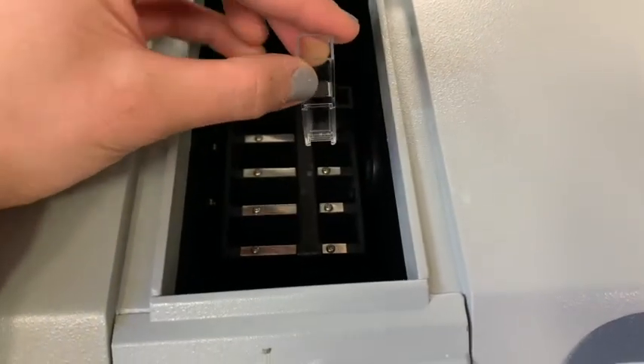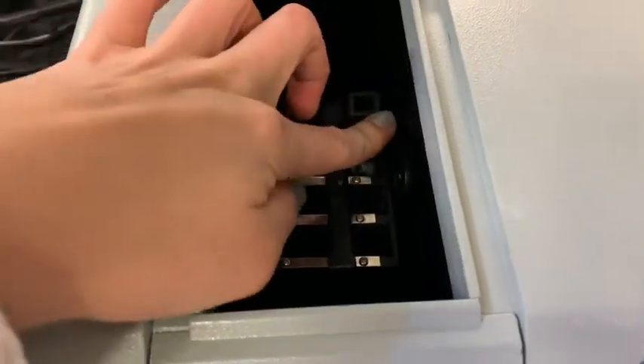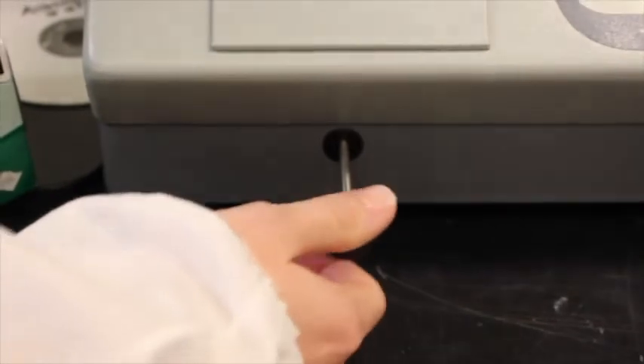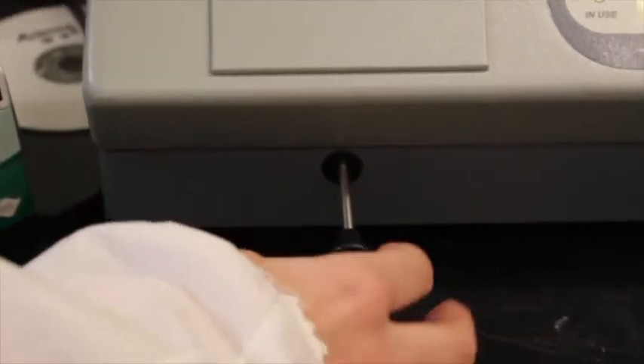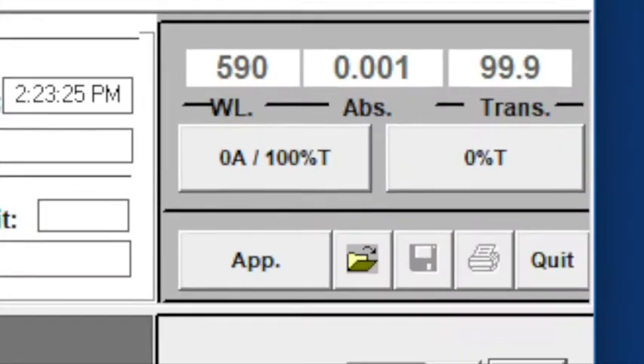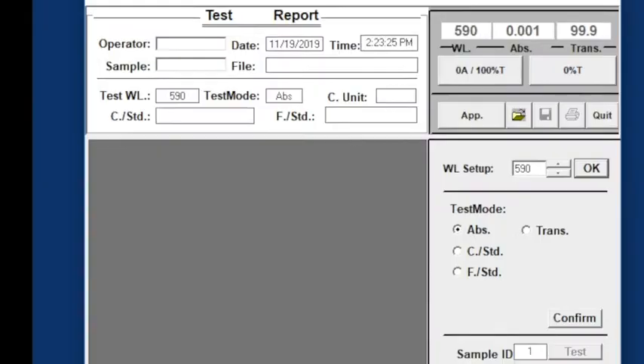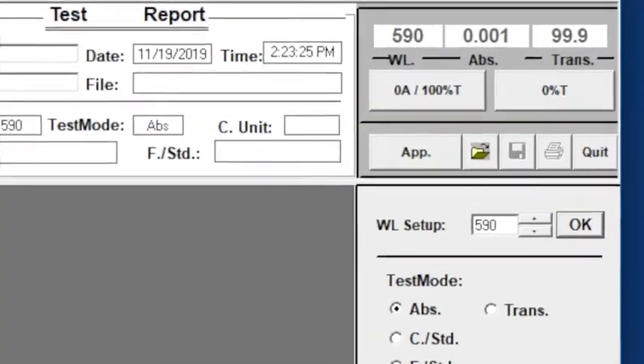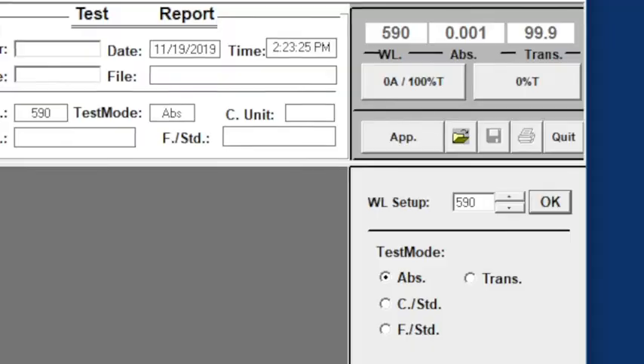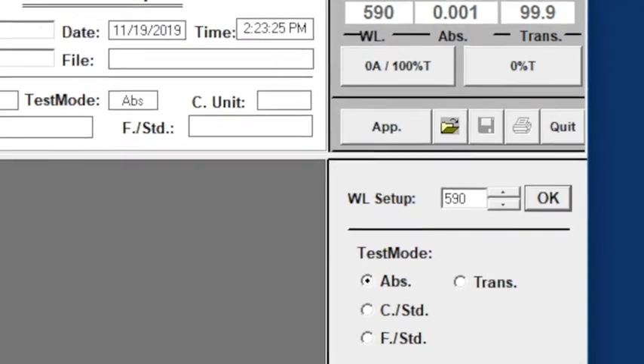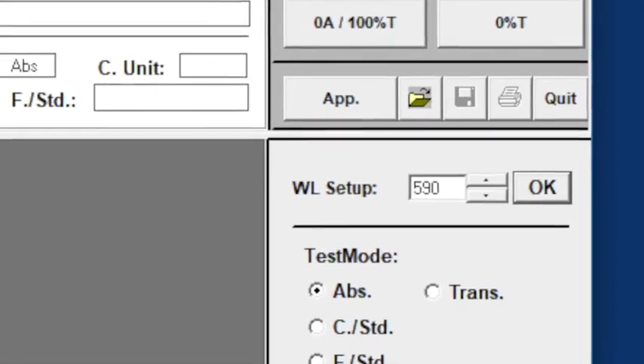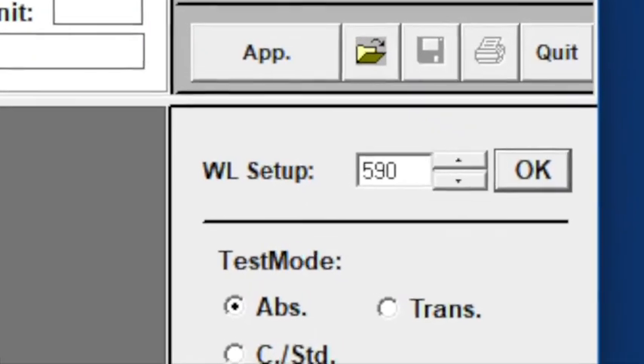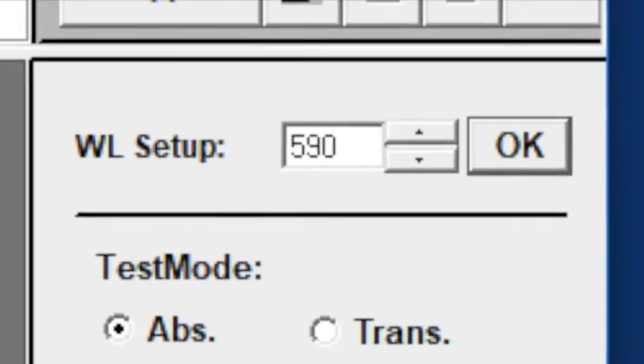It is important to use the same slot throughout the entire experiment. Set the dial to record the correct slot. Press 0A/100% T. The system will now allow you to set the wavelength. Type the desired wavelength to 590 nanometers in the WL setup box. 590 nanometers is the peak wavelength of crystal violet dye.